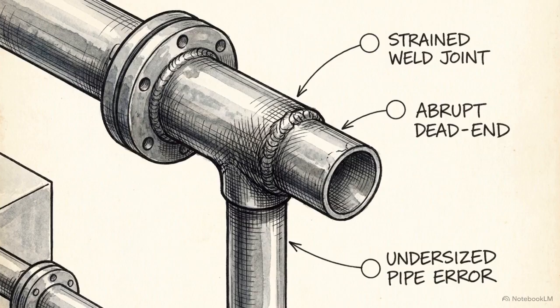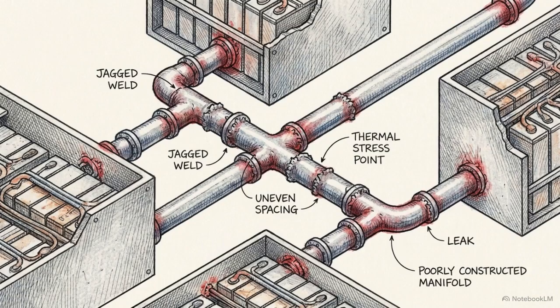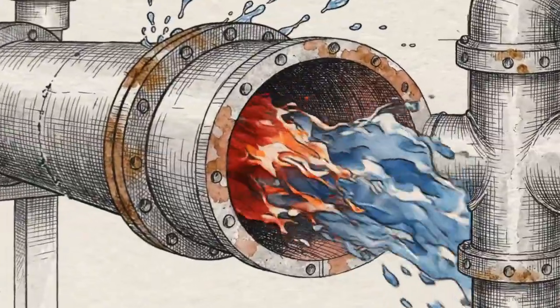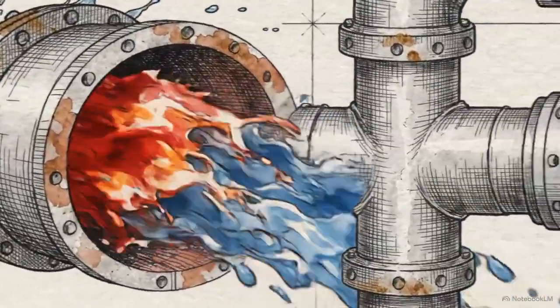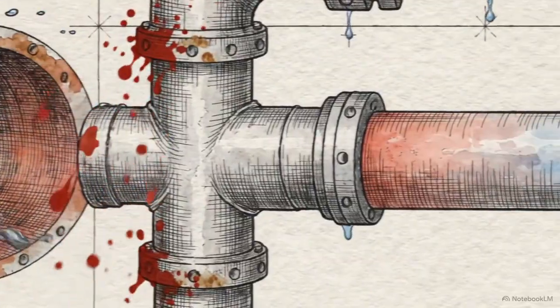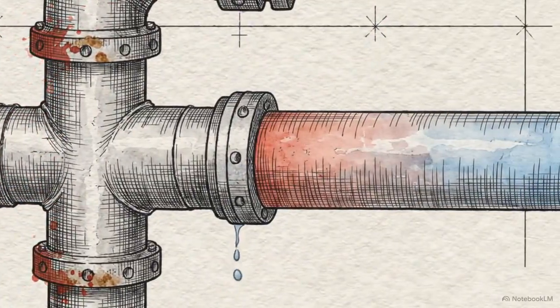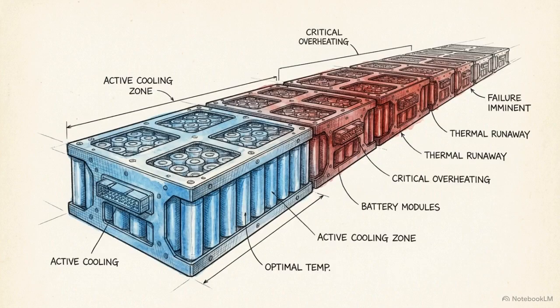But perfect digital logic will fail if the underlying physical architecture is flawed. One of the most critical mechanical errors is poor manifold distribution, where the pipe splitting fluid to the battery racks is incorrectly sized. An unbalanced manifold forces the vast majority of the coolant into the closest battery modules, starving the modules at the end of the line. The first batteries freeze, while the remaining units overheat and trigger system alarms.